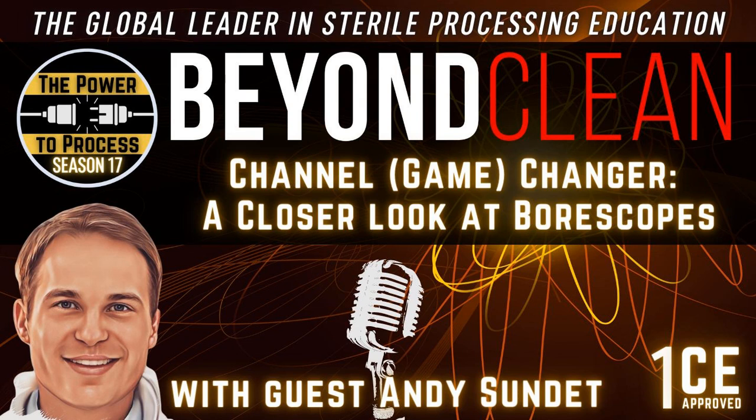So borescope companies have been learning along the way. As we've been seeing more users of borescopes, we learn what lumens they're going into, what's inside those lumens, and how we can build a better borescope to handle this daily activity. The distal tip, where the camera and the light are, going through, say, a suction that's like sandpaper on the inside 1,000 times in a year, is pretty tough on a borescope. So that's where the other damage was. And I think some of those enhancements have made them more durable. Everyone's trying to make these things more durable.